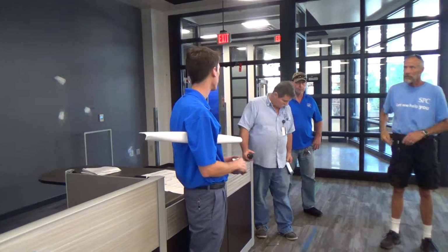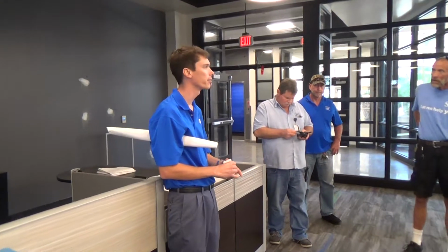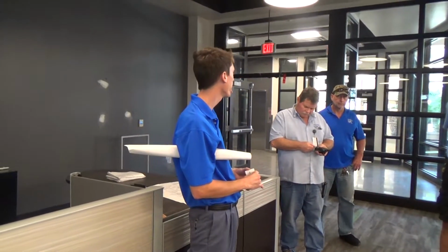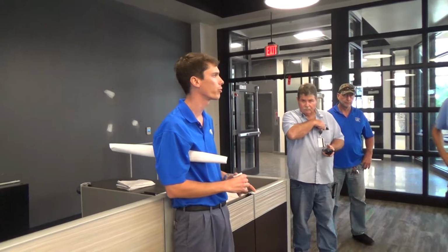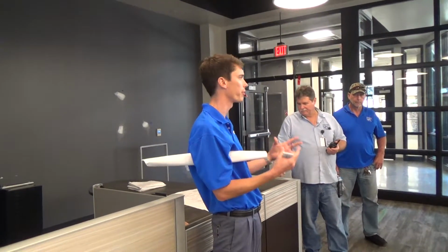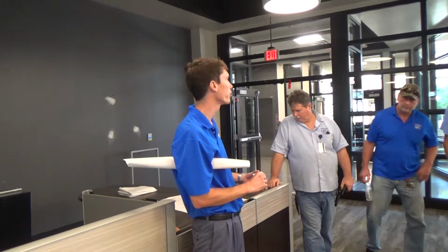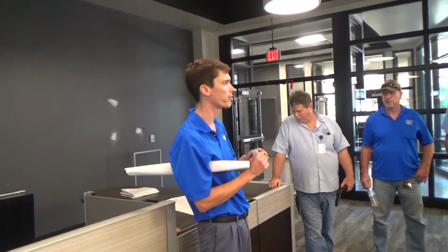Scott and I are with Envision Lighting Systems, and we provided the lighting and lighting controls to Pelican to be installed here. And you guys are probably used to relay panels. You get your old relay panel coming from the breaker box, and the relays control when to turn lights on and off. And this is a similar situation to that, except the relays are distributed.